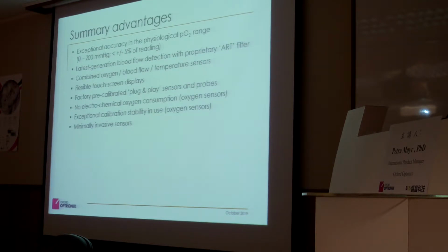Because we're in a bit of a rush today, we're working in the physiological range. The laser Doppler, which I haven't spoken much about, has a special filter inside which, if you measure vital organs, removes the breathing artifacts and movement artifacts. With the oxygen that's not so crucial, but it's important in the laser Doppler. We offer the combined sensors. You can work with the instrument with the touch screen. Sensors are pre-calibrated, the laser Doppler sensors too. There's no oxygen consumption, and the calibration stability is 1 year.